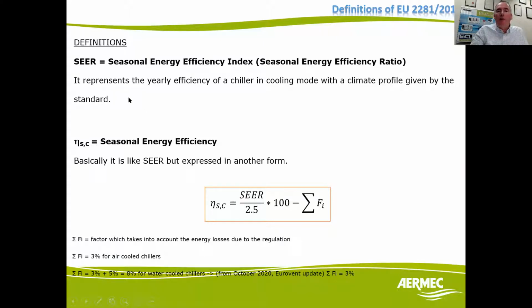So the SEER, which is the seasonal energy efficiency ratio, is a little bit more comprehensive than the old-fashioned ESEER. I'm sure most people know EER, by the way, is your energy efficiency ratio, which was basically relating to 100% cooling capacity, 100% input. One divided by the other is the efficiency. So if you have 300 kilowatts of cooling capacity and 100 kilowatts of absorbed power, your EER would have been 3.